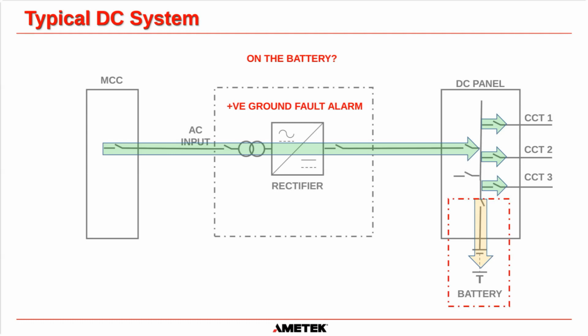But the easy way, once again, we've still got the ground fault alarm on. We just open this breaker here, okay? Is it on the battery? If we disconnect the battery and the ground fault alarm goes away, then the fault is on the battery. You found it, okay? If you open the breaker and the ground fault alarm remains on, now we know it's either in the DC panel or it's on the load circuits.